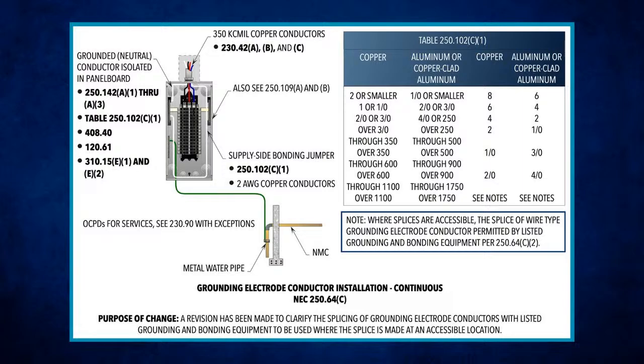But if I have a concrete encased electrode, and then I tie it into the building steel, that is not an electrode, Jeremy. So it's basically getting bonded in, but yet I'm using the concrete encased electrode. So if I go over there to that building steel and I bond into it, which is going to tie it into the concrete encased electrode, what size do you need? Number 4. 100%.